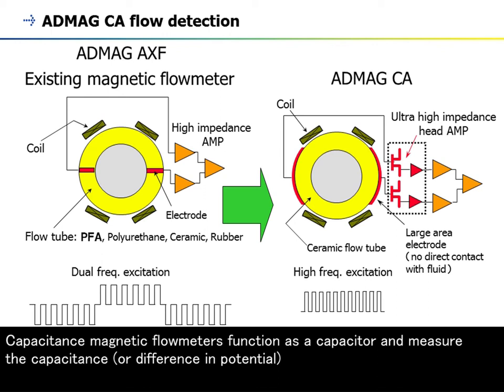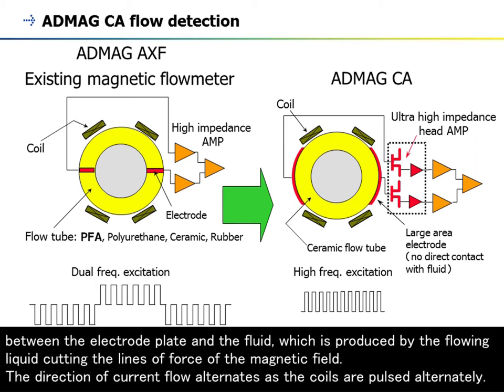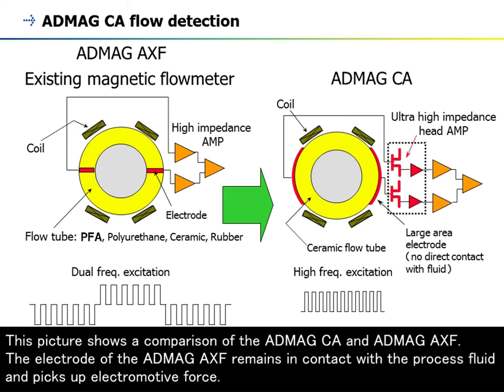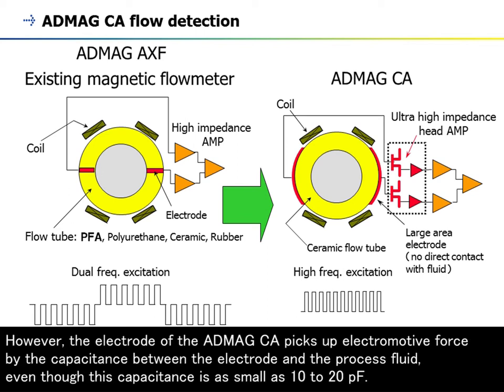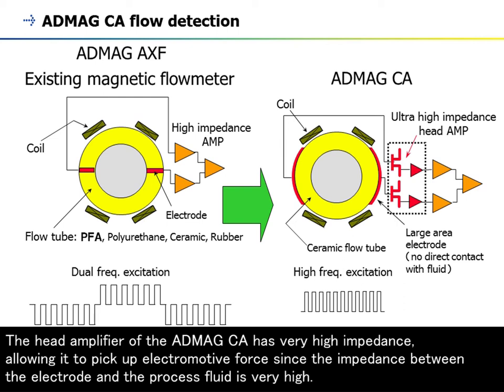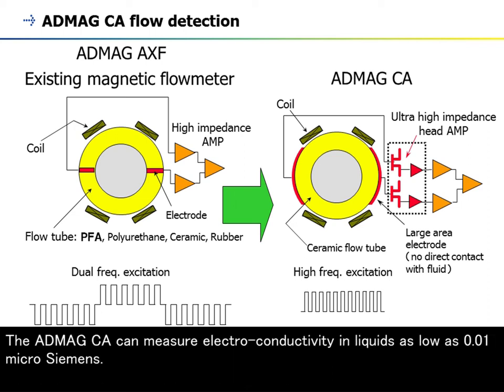Capacitance magnetic flow meters function as a capacitor and measure the capacitance, or difference in potential, between the electrode plate and the fluid, which is produced by the flowing liquid cutting the lines of force of the magnetic field. The direction of current flow alternates as the coils are pulsed alternately. This picture shows a comparison of the ADMAG CA and ADMAG AXF. The electrode of the ADMAG AXF remains in contact with the process fluid and picks up electromotive force. The electrode of the ADMAG CA does not come in contact with process fluid; however, it picks up electromotive force by the capacitance between the electrode and the process fluid, even though this capacitance is as small as 10 to 20 pF. The head amplifier of the ADMAG CA has very high impedance, allowing it to pick up electromotive force since the impedance between the electrode and the process fluid is very high. The ADMAG CA can measure electroconductivity in liquids as low as 0.01 microsiemens.